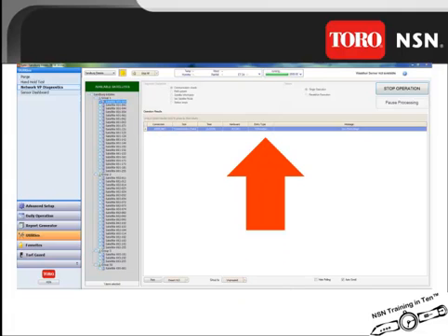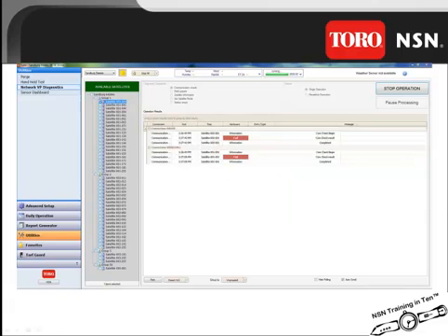If it is successful, it will show here as a successful communication. If the operation fails, it will show here as well. If this occurs, check all the satellites. If it is a consistent process, then check the field interface unit. If the field interface unit is working properly, check the outputs to the field. If that seems to be working properly, check the satellite power supplies or the modem boards. If only a single satellite fails, then go directly to that satellite to make sure it is functioning properly.